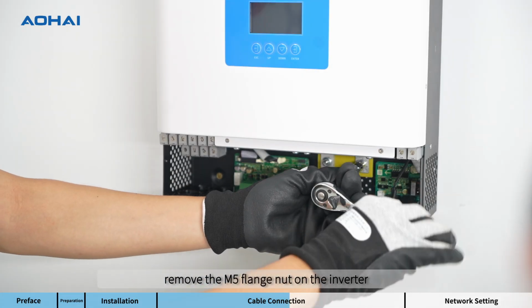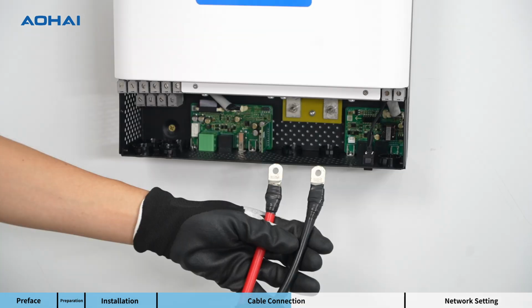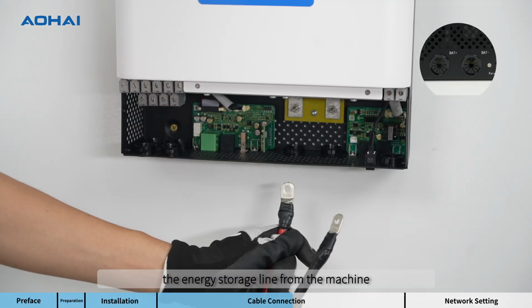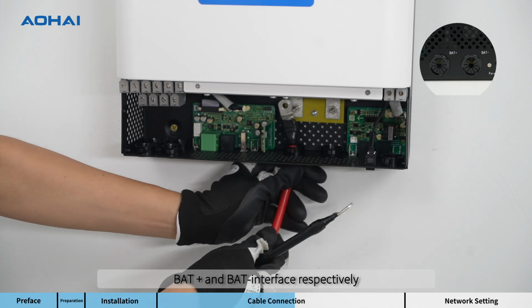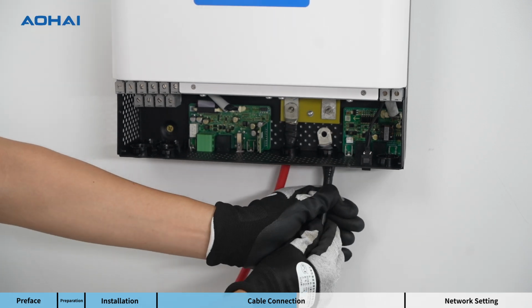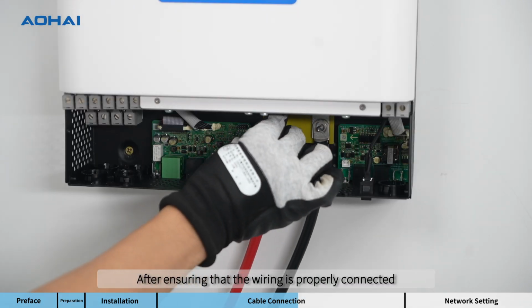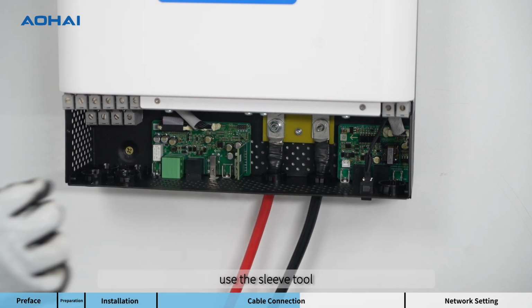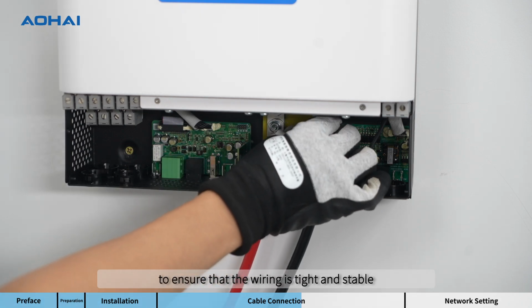First, remove the M5 flange nut on the inverter. Then, connect the energy storage lines to the BAT+ and BAT- interfaces on the machine respectively. After ensuring that the wiring is properly connected, use the sleeve tool to ensure that the wiring is tight and stable.